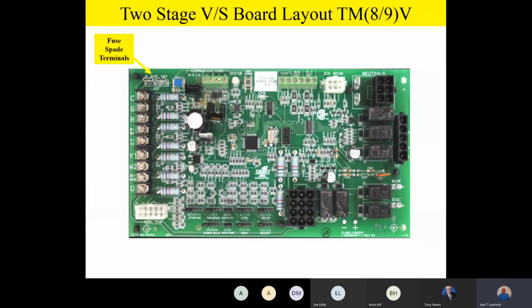At the top of the board, we see we've got our fuse spade terminals. I don't know why I don't have a fuse on this photo, but 5 amp maximum, and we typically ship all of our boards with a 3 amp fuse, but 5 amp maximum on this board. As we move around the top of the board, team, you're going to notice there's some communication screw terminals. That's if you want to have this furnace set up with a 4-wire communicating system. So again, from our thermostat on the wall, you'd have 4 wires coming down to A, B, C, and R for communicating capable. So this is a communicating capable board, or you can hook it up 24 volt.